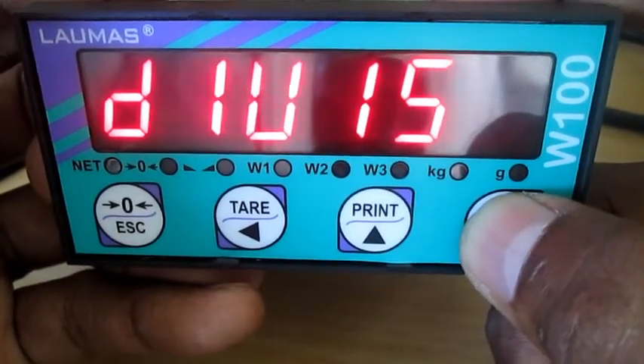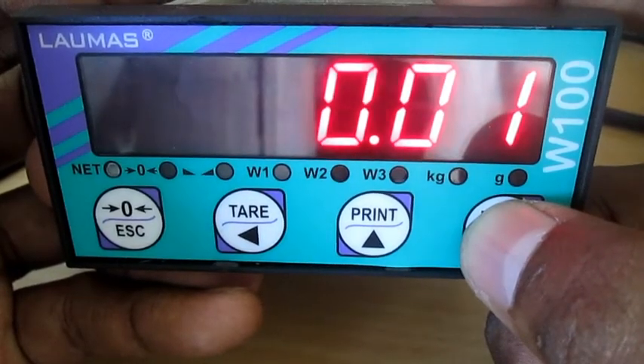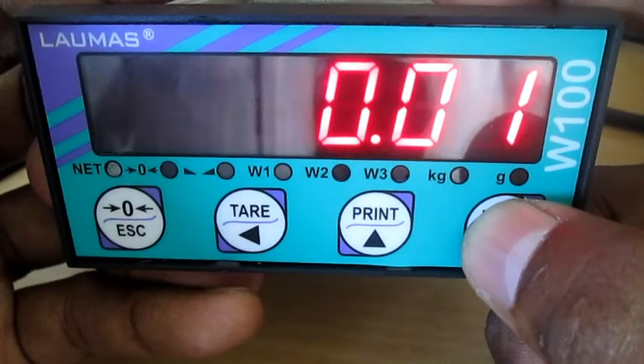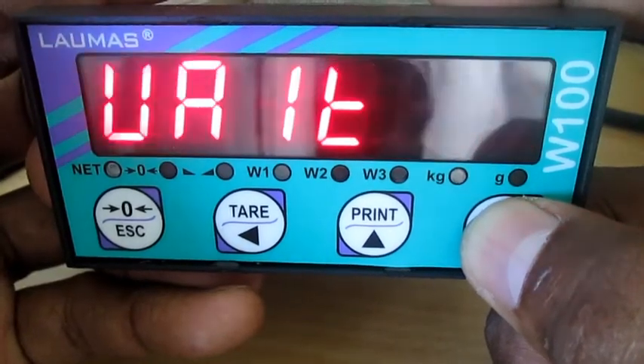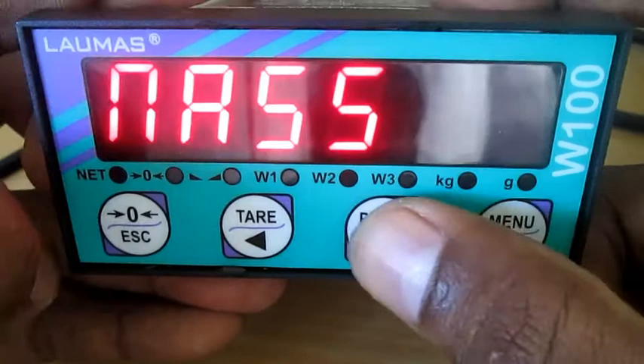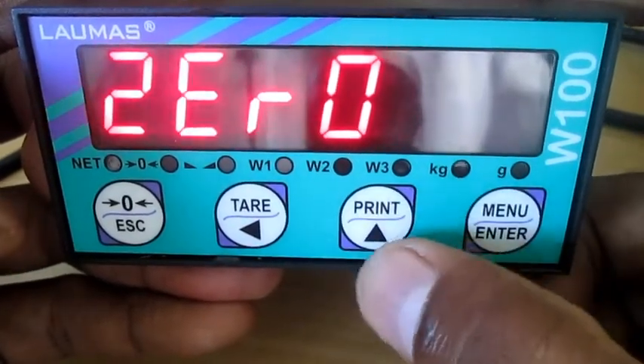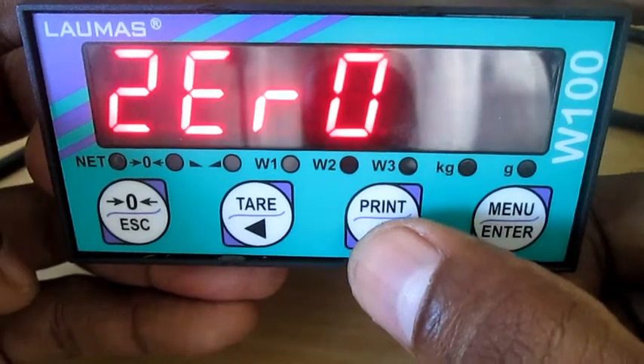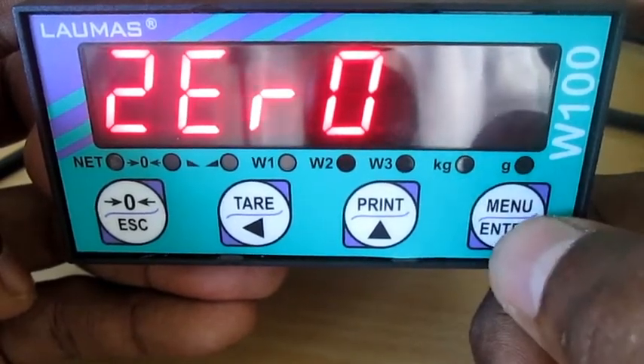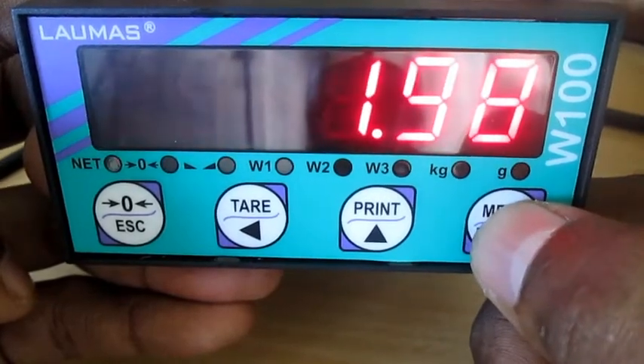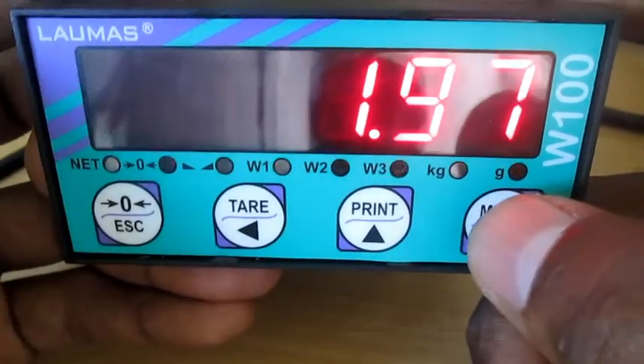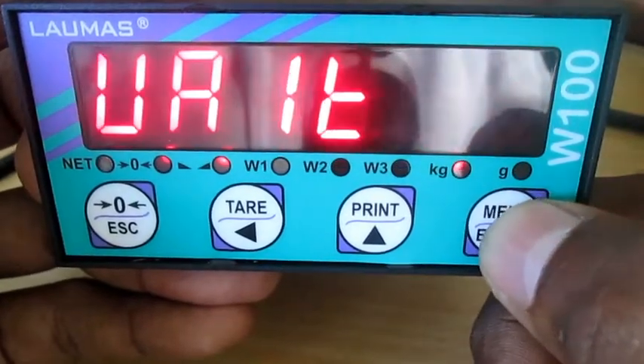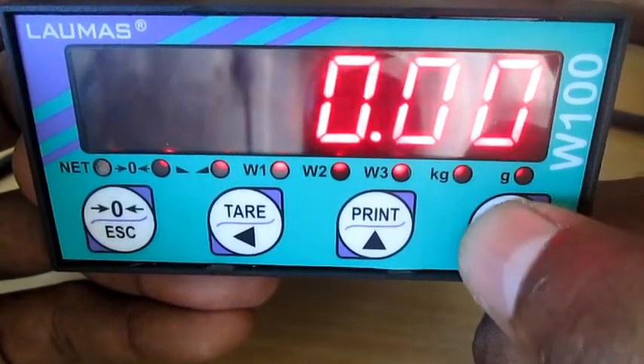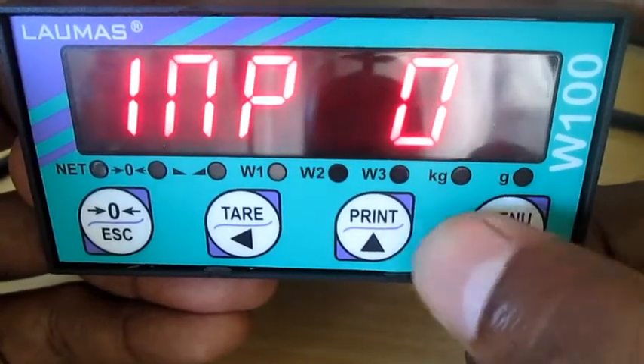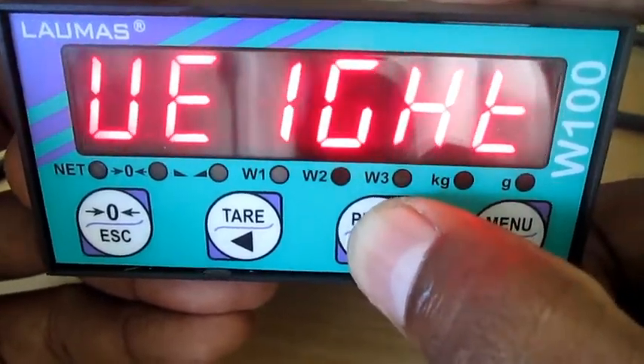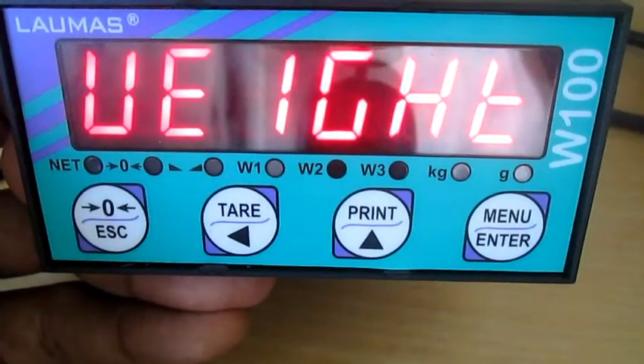Display division is automatically calculated as per the metrology, 0.01 kg. We are just confirming, and then we are changing the menu to 0 for making 0 calibration, acknowledging using menu button. Display reads 1.98 kg. I am giving OK command to confirm 0 kg, and then once again I am confirming. Display comes to input 0. I am scrolling into weight menu to do calibration.